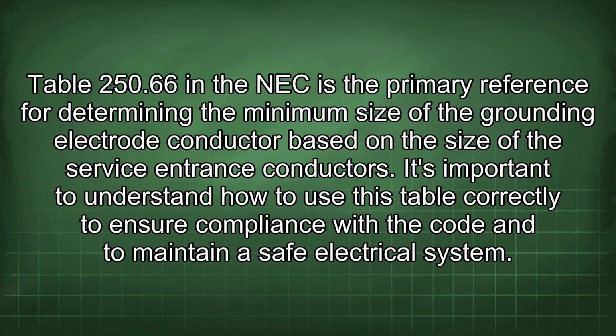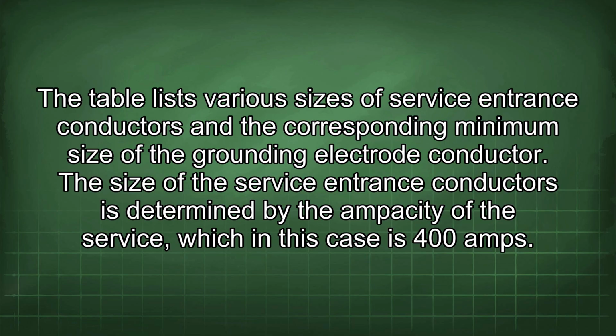Table 250.66 in the NEC is the primary reference for determining the minimum size of the grounding electrode conductor based on the size of the service entrance conductors. It's important to understand how to use this table correctly to ensure compliance with the code and to maintain a safe electrical system. The table lists various sizes of service entrance conductors and the corresponding minimum size of the grounding electrode conductor.